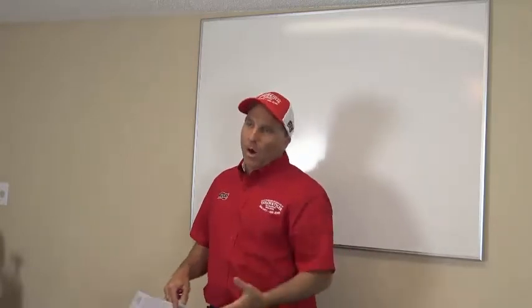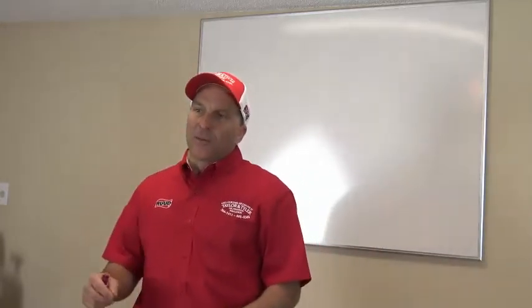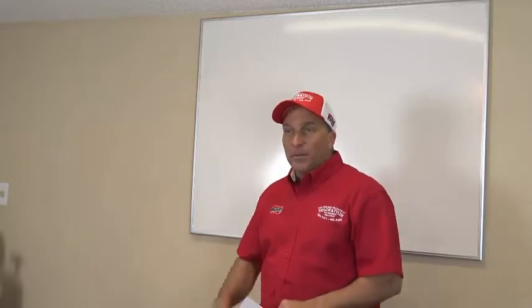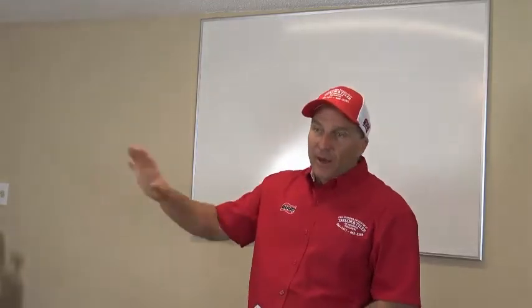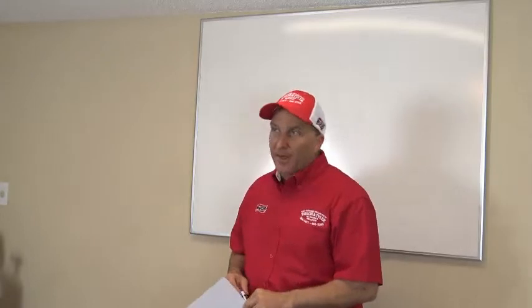Most of the time, it's got water on it all the time. How many times have you seen a compressor sweat about that much just by the suction line? That's the way it's supposed to be. Put a silver dollar around it, and there's your sweat on that compressor. If you see that whole compressor sweating, then it's sucking in liquid. There's a problem. The problem could be numerous things. I'm not going to get into that. That'll be other videos for low superheat. So check the video out for low superheat, and that'll tell you all the things that can make that compressor sweat. All right?